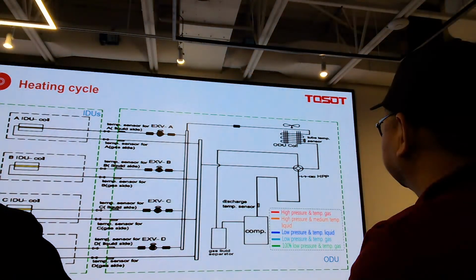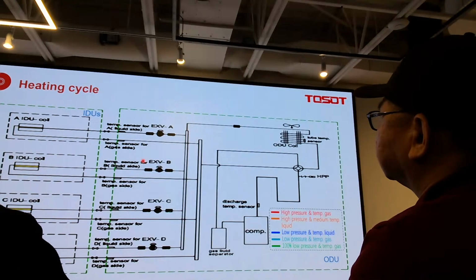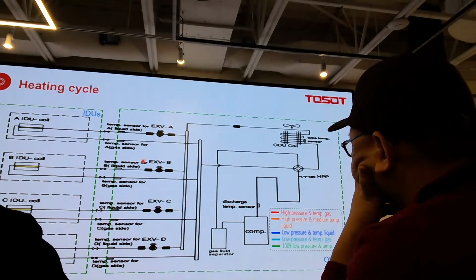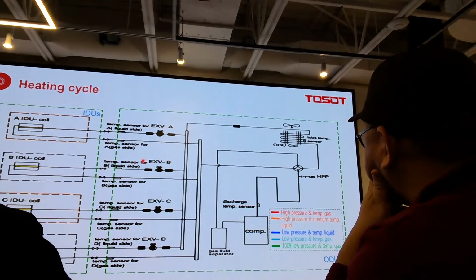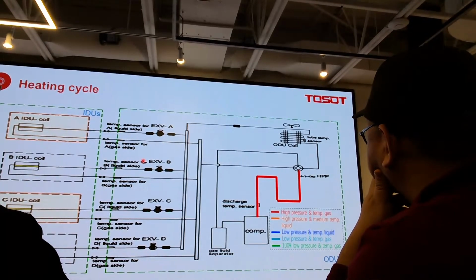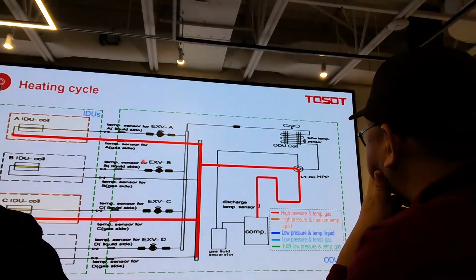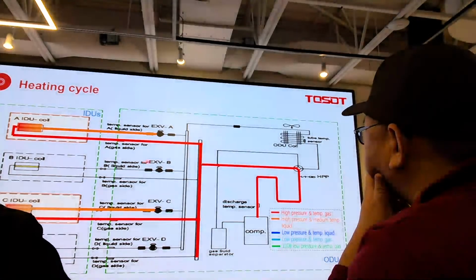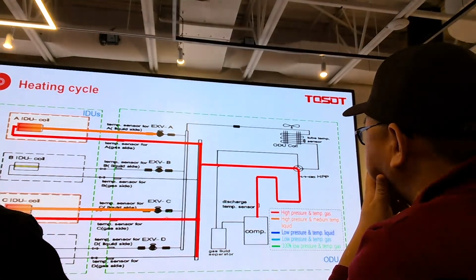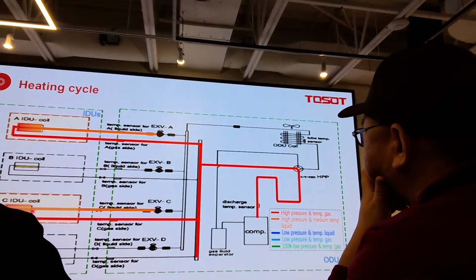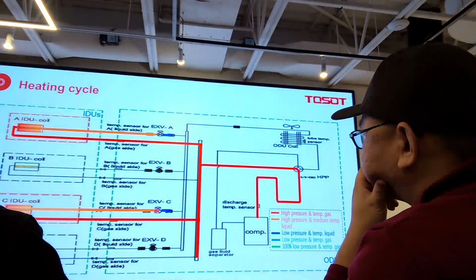This time for heating, the wiring and piping sequence is almost the same. So let's analyze how the refrigerant flows first. This time, assume indoor units A and C are called for heating. The refrigerant will flow to the indoor side first. Then after releasing heat it becomes liquid and flows back to the outdoor unit. And only at A and C will we do the metering. So like this.